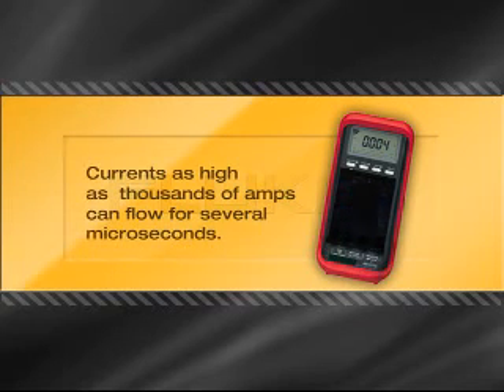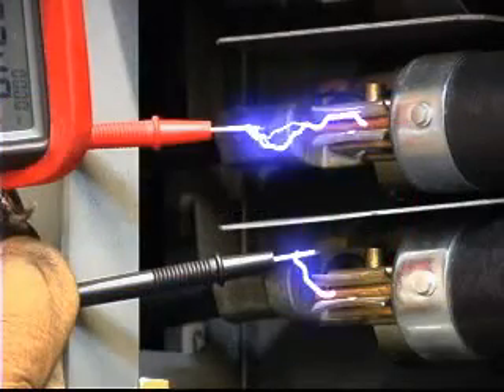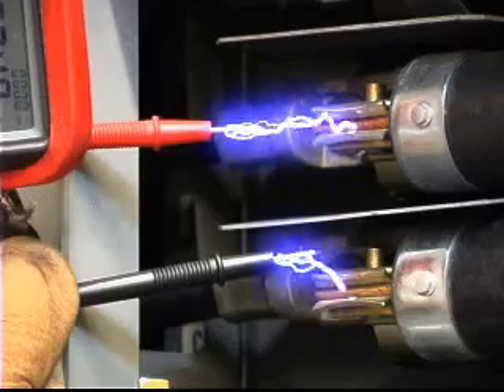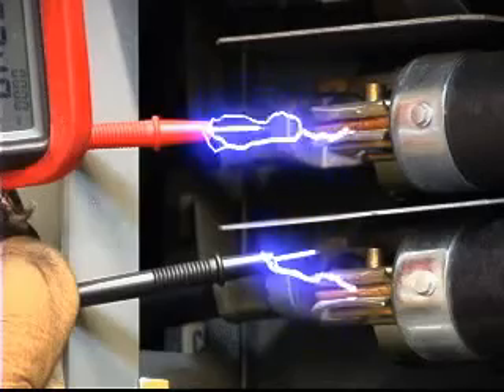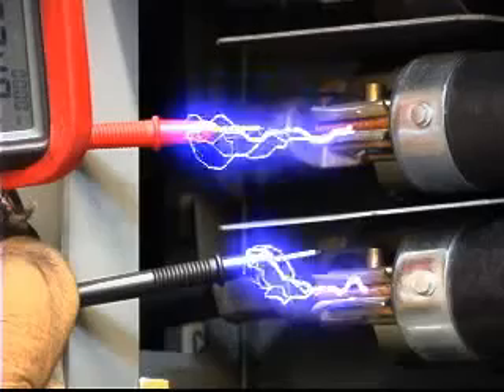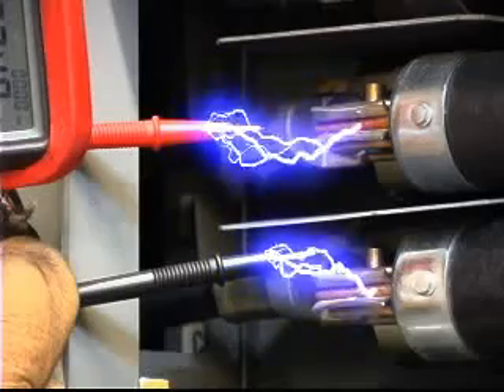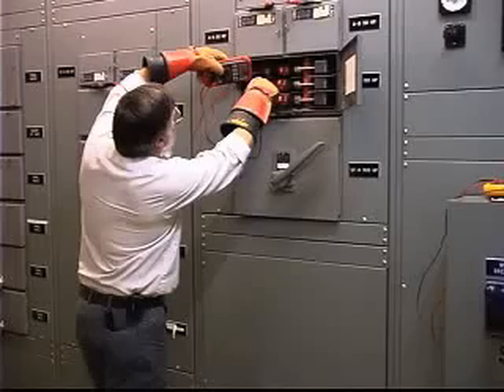Short-circuit currents as high as thousands of amps can flow for several microseconds. At these current levels, the tips of test leads superheat, and the handheld probe tips start to burn away, drawing an arc from the contact point to the probe tip. The tech sees a bright blue arc flash, and at the same time is startled by the bang of the arc exploding inside the meter. The arcs follow the vaporized test probes.